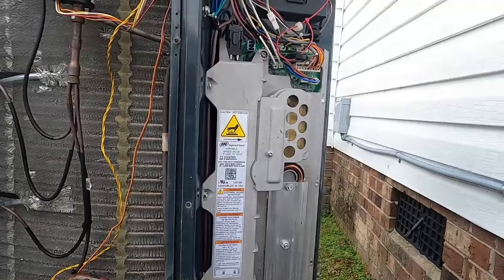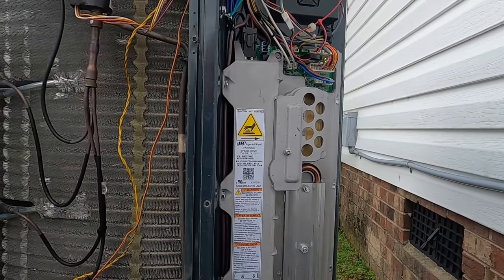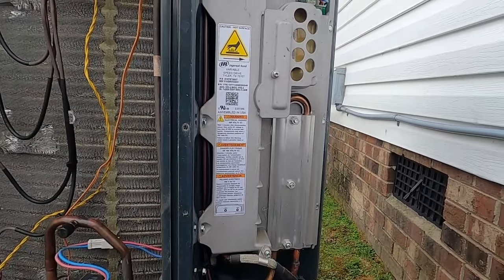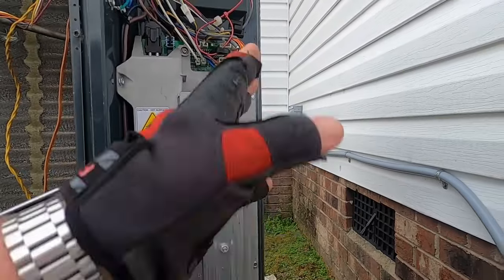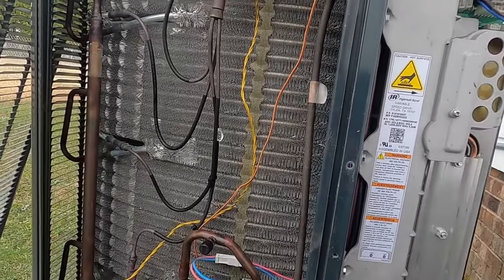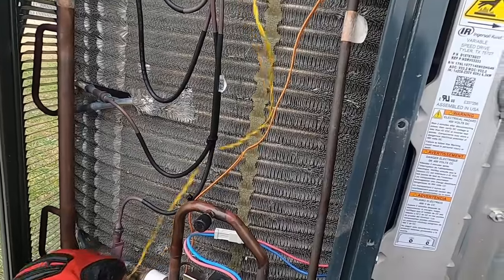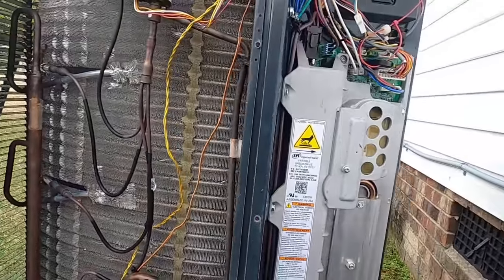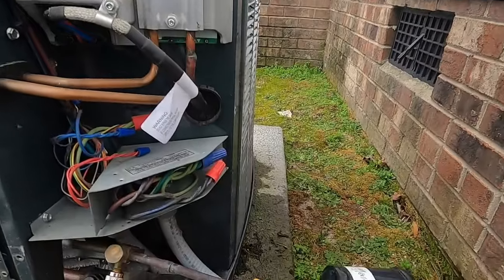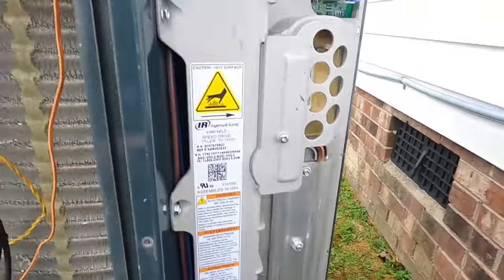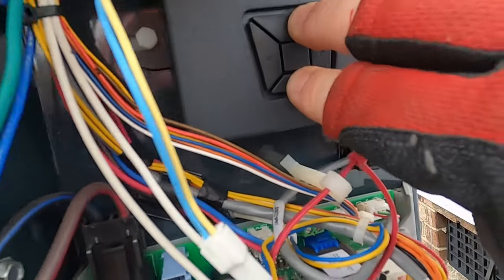But that's why you always watch the equipment run before you leave, so you don't leave anything turned off. With one of these, that's not a situation where you want the homeowner coming out and turning power back on. You really want to be here and make sure it powers back up like it's supposed to. So let me pull up the gauges. Let me go in here and see what speed we're running at.